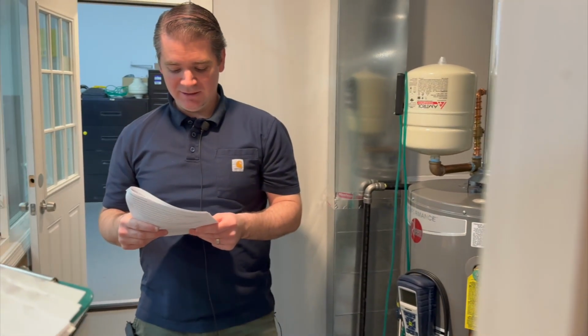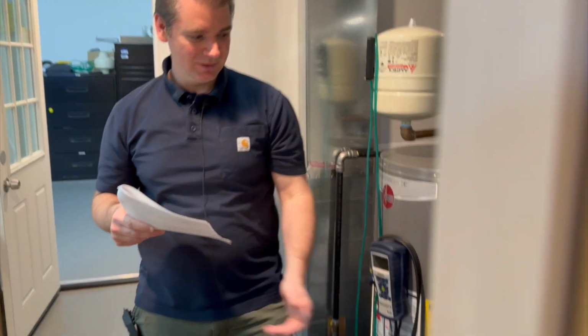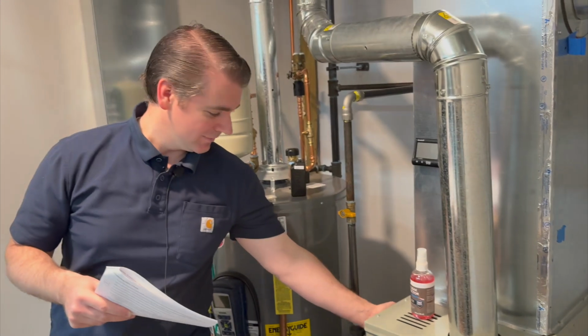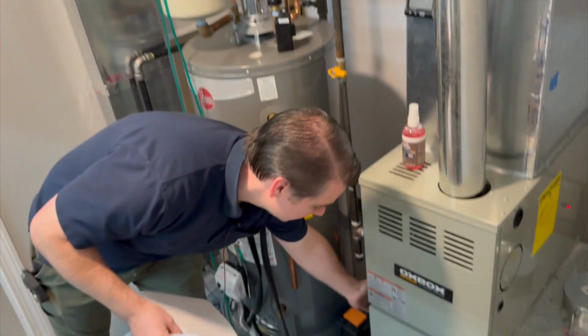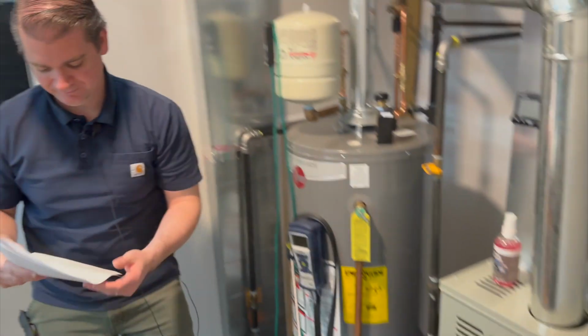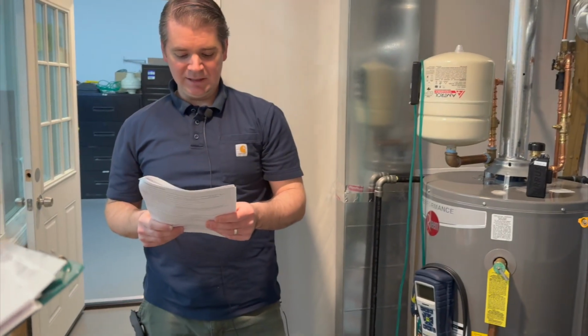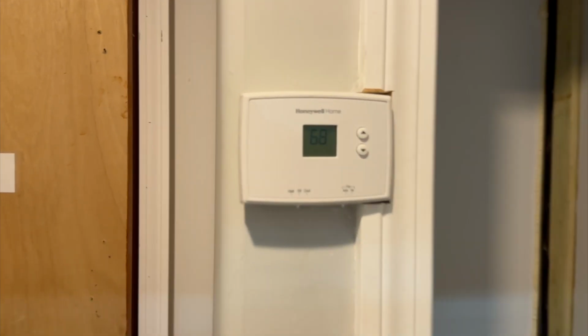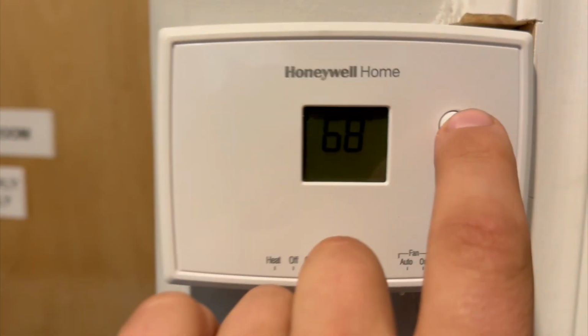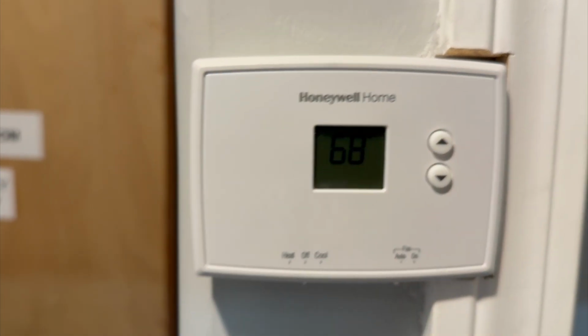Identify 3 basic heating system components. We have the cabinet. Back behind here, we've got our heat exchanger. And then down below, we have our blower motor. Identify the controls and how the set point controls the system cycling. Looks like we have our thermostat right around the corner. If we set our thermostat to 70 degrees, it's going to send a signal to the furnace. It's going to fire up and heat up the house until the thermostat is satisfied that we've reached that 70 degrees, then it will turn off again.